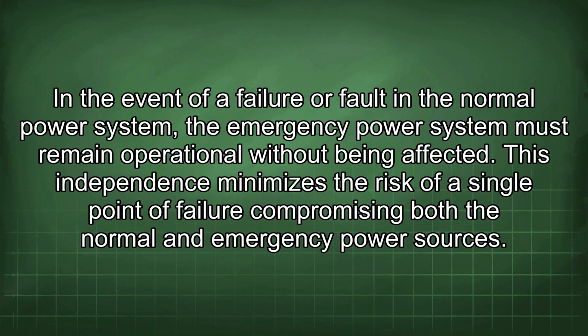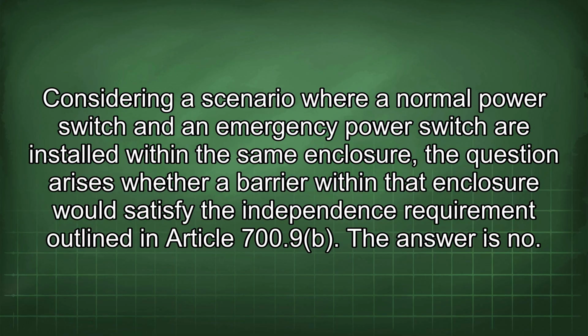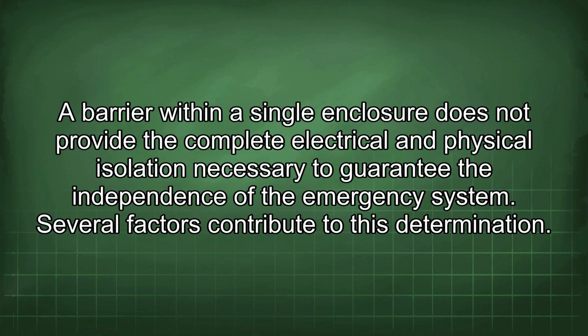This independence minimizes the risk of a single point of failure compromising both the normal and emergency power sources. Considering a scenario where a normal power switch and an emergency power switch are installed within the same enclosure, the question arises whether a barrier within the enclosure would satisfy the independence requirement outlined in Article 700.9. The answer is no. A barrier within a single enclosure does not provide the complete electrical and physical isolation necessary to guarantee the independence of the emergency system.